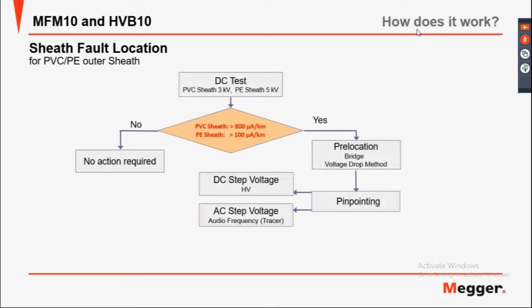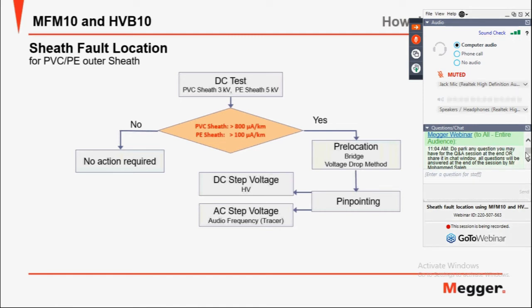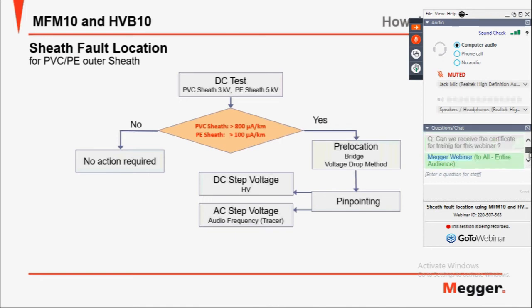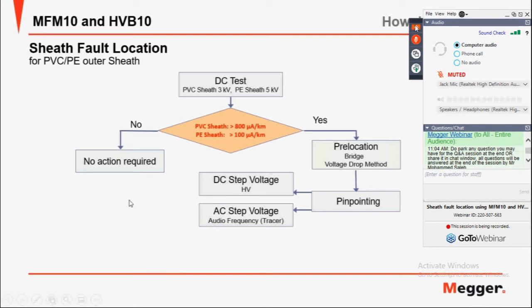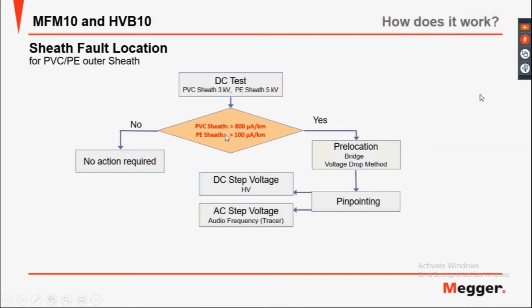Sheath fault location workflow: PVC, PE outer sheath. PVC sheath test at 3 kV, or PE sheath test at 5 kV, depending on the current and voltage it holds. If it holds, no further action required. If the sheath current is more, then use the bridge fault method. Check whether an auxiliary wire is available, and if so, determine if pinpointing is possible and whether the cable is in a duct.